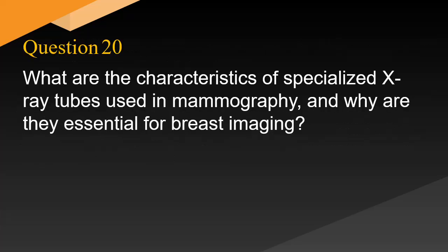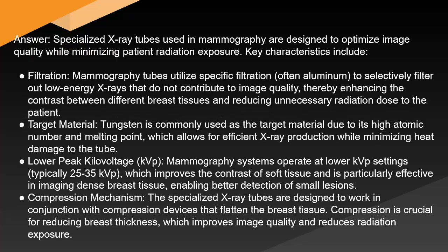What are the characteristics of specialized X-ray tubes used in mammography, and why are they essential for breast imaging? Answer: specialized X-ray tubes used in mammography are designed to optimize image quality while minimizing patient radiation exposure. Key characteristics include filtration.